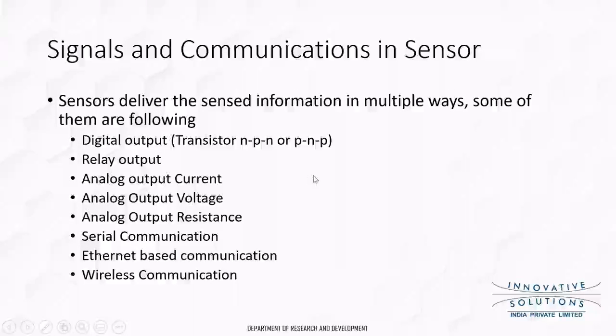Then there's analog output - current source and current sink are very common sensor types in industry. They give a constant current value, typically in the 4 to 20 milliampere range. For example, if a sensor's range is 0 to 100 degrees Celsius, at 100 degrees it gives 20 milliamperes, and at 0 degrees it gives 4 milliamperes - that's a constant current or analog current output sensor. There's also constant voltage or analog voltage sensors, which give voltage in the range of 0 to 10 volts or 0 to 24 volts.